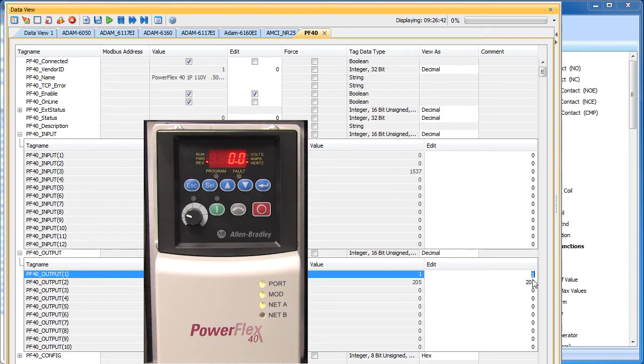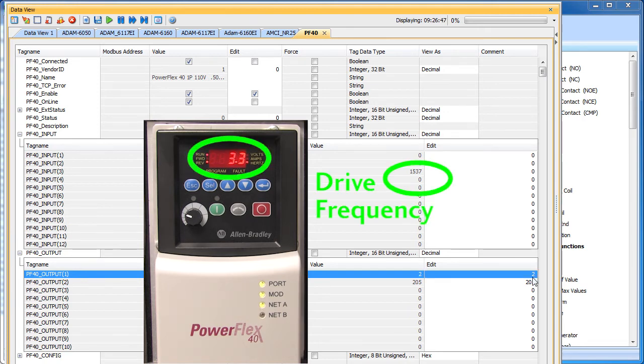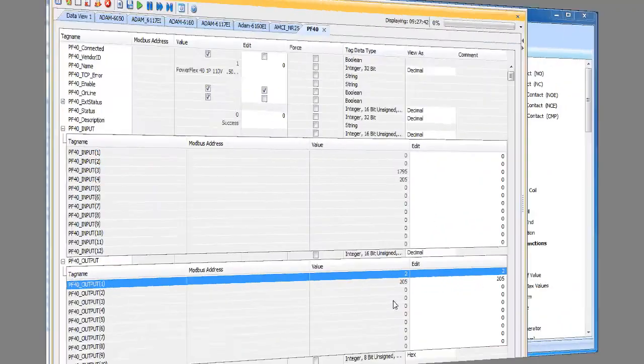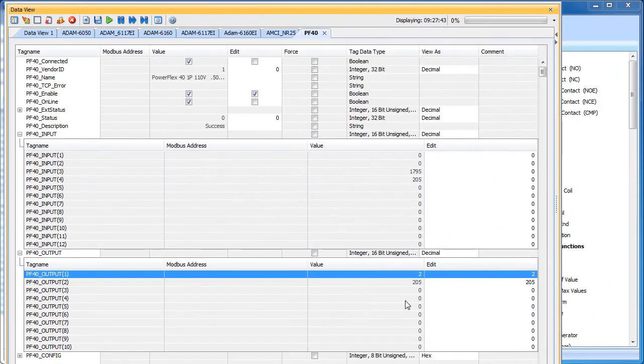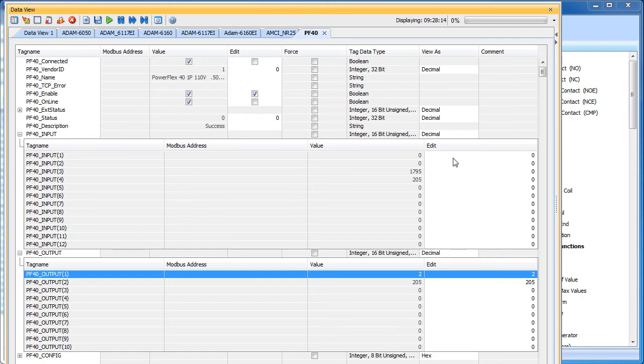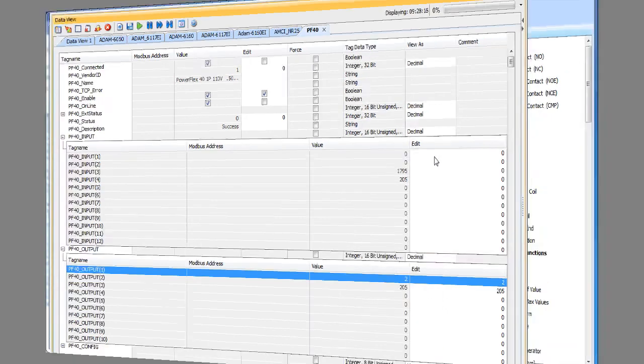Let's turn the drive back on for one second. Again, I'm just going to enter a 2 and hit return. You can actually see the frequency right here in our input array. Now normally your ladder code would be the one flipping these bits and changing these values of course. We've intentionally used the Data View to do it here just to make the point that all of this data transfer happens independent of your ladder code. We haven't written one rung of ladder code yet, have we? But when you do write your ladder code, all you have to do is manage these local arrays and the Ethernet IP Implicit Messaging takes care of transferring the data back and forth for you in the background.